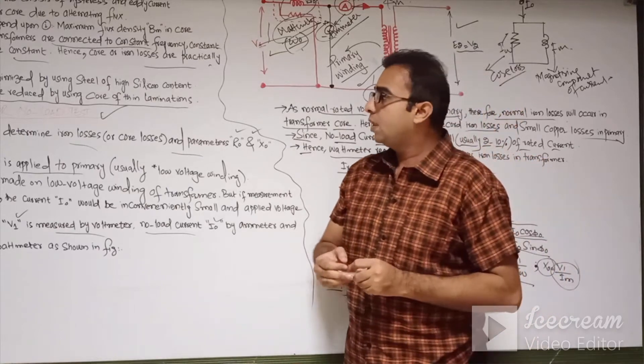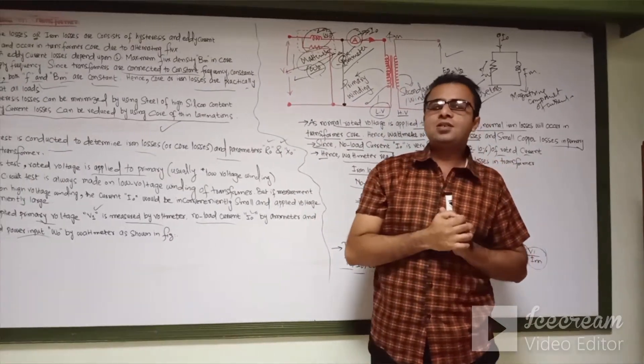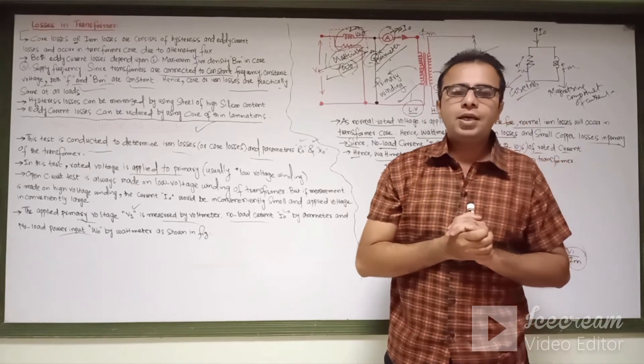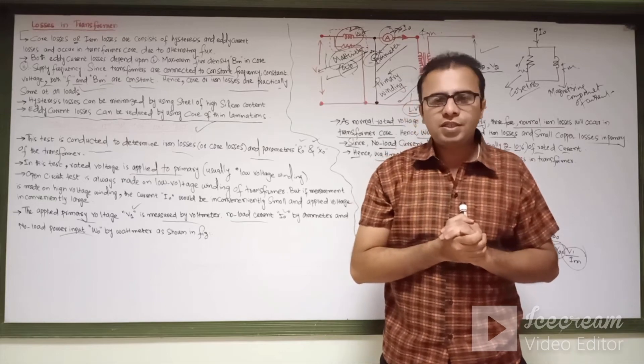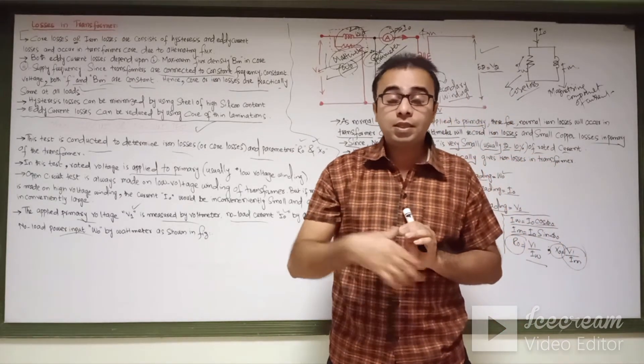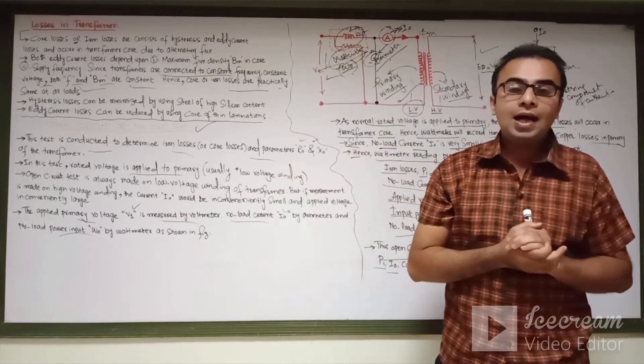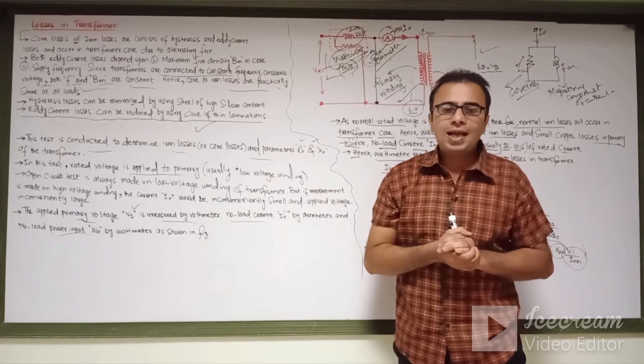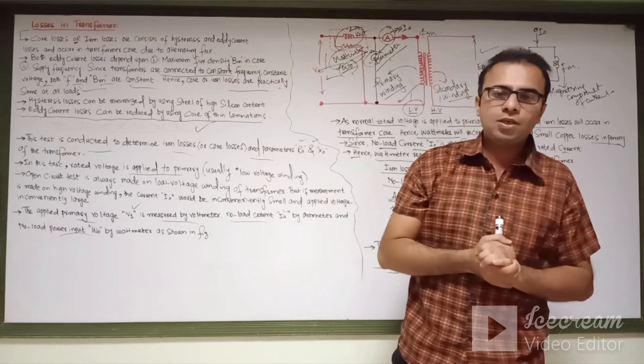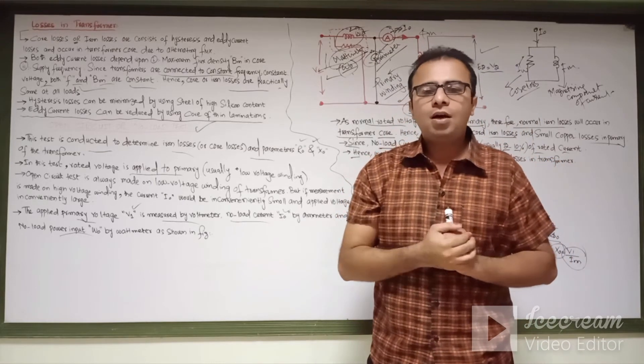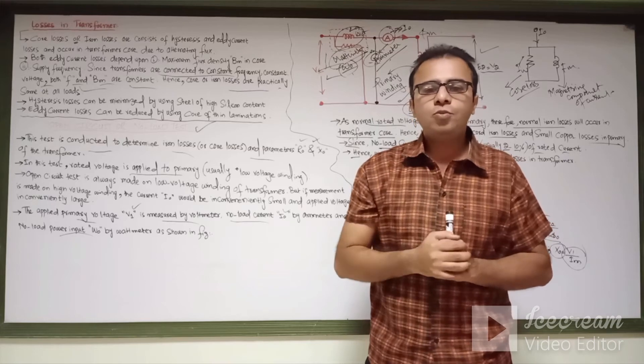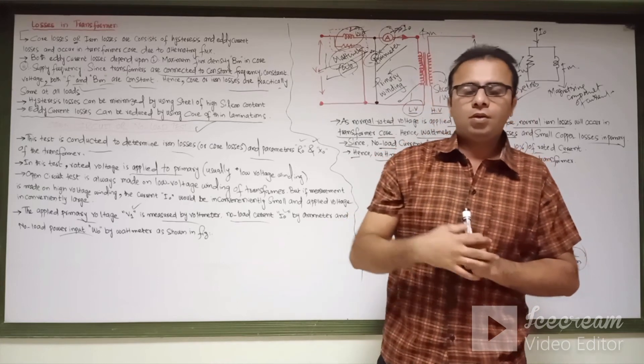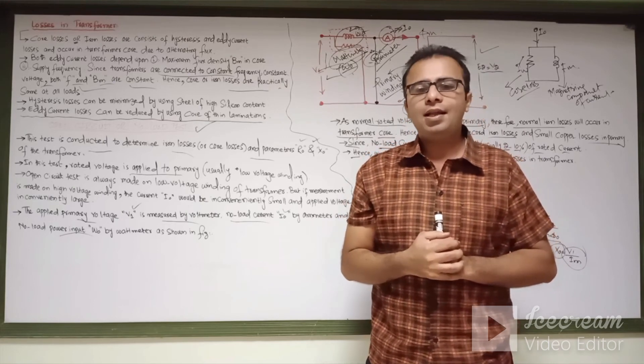To summarize: the open circuit test of the transformer is used to determine the iron losses or core losses in the transformer. This test is conducted on the low voltage winding, with the high voltage winding kept open circuited according to the circuit diagram. Please don't forget to subscribe to my YouTube channel and hit the bell icon to watch more videos related to electrical engineering and electrical machines. Thank you.